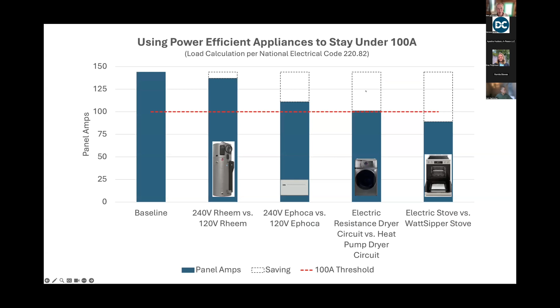The highest average peak we found was 12 amps. You can see that one just to the left, roughly 3,000 watts. That's the wattage on the side, you divide it by 240 volts to get the amps.